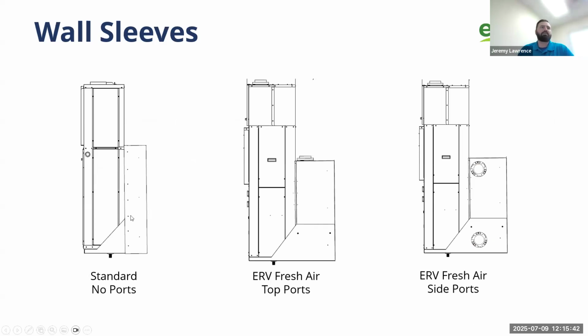Side view, like I said, the rear access sleeve has this triangle support that carries the weight of the unit, with a 3/4 inch MIP fitting coming off the bottom of the sleeve for easy drain connection. In this Eco Series, without the built-in ERV, there's a standard duct connection off the top. The ERV units, the Fresh Pack units, what First Company has done is actually built the sleeve so that the ERV ports are integral right into the sleeve connection as well. So we use the condenser fan motor to assist in ventilating the ERV, acting as a concentric vent kit. So we maintain no mixing of fresh and stale air, but we don't need two more wall penetrations for an exhaust and an intake fresh air. That all can be done as part of the sleeve. Both top and side ports are available, but just because of trying to keep the closets as small as possible, fresh top ports have certainly been the most popular over the last few years.